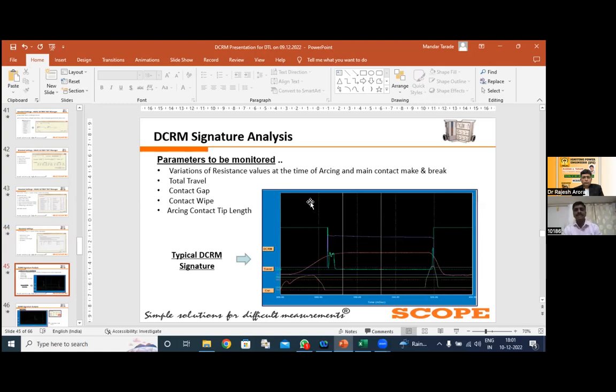Now moving further, DCRM signature analysis. This is very important, and I just want to repeat once again what parameters we are able to analyze with the help of DCRM. First, basically the value of the resistances, or the variation in the value of the resistances at the time of making and breaking, that is, of the arcing contact as well as the main contact. Second, we get the value of the total travel. Third, the value of the contact gap. Fourth, the value of the contact wipe. And fifth, and important, the arcing contact tip length.